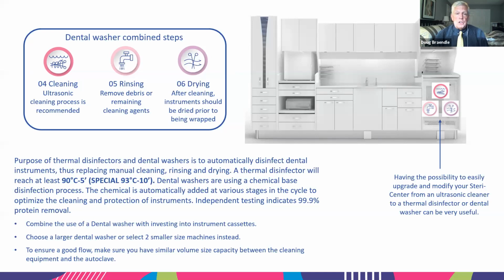It'll get washed. It'll get rinsed first, then it'll get washed, then it'll get rinsed for a final time and then dried. So when you open up the door, all the instruments, all the cassettes are dry and ready to go. And Annie was exactly right. Wet instruments going into anybody's sterilizer, we kind of have a rule of thumb, especially if it's a pouch. Wet pouches going in is going to get you wet pouches going out of a sterilizer.